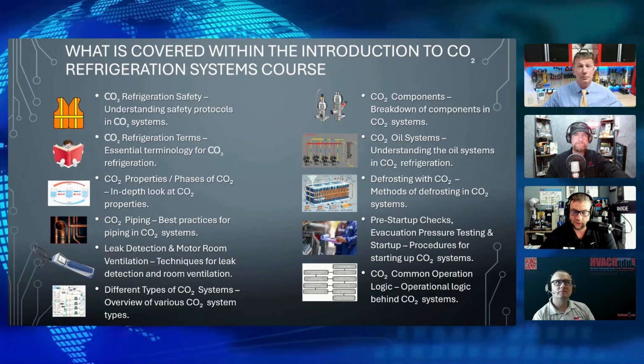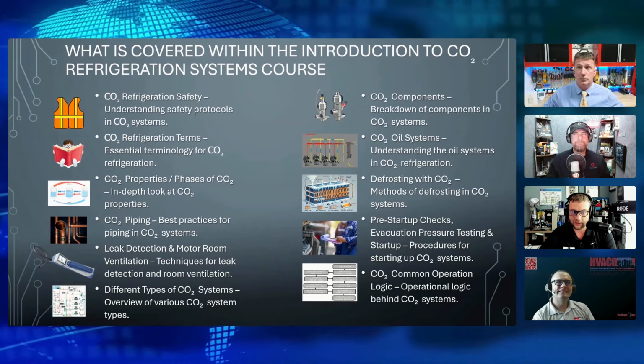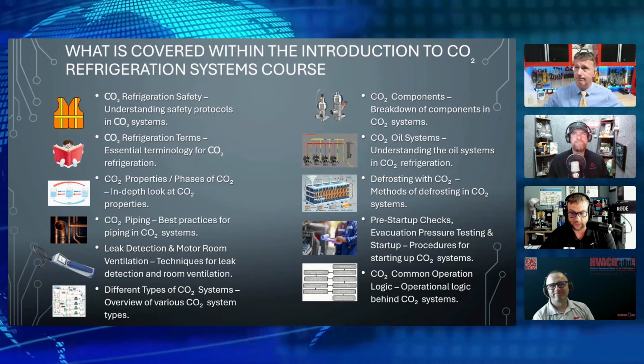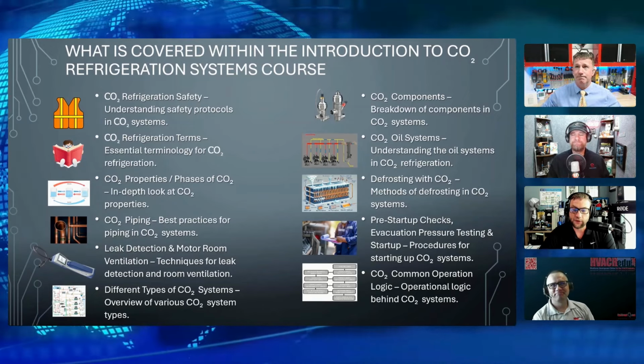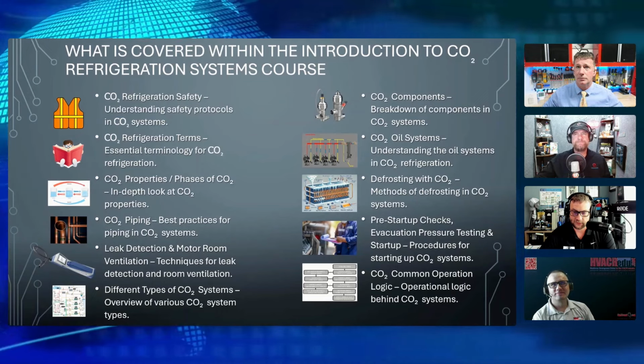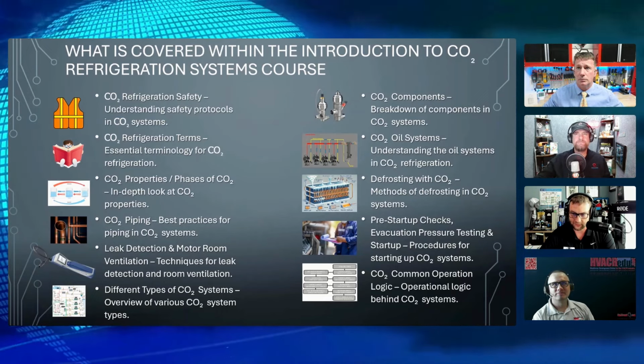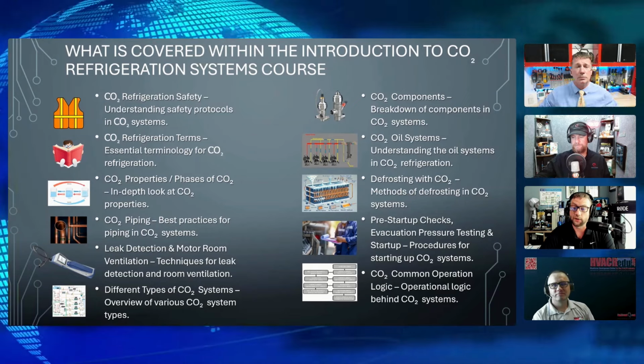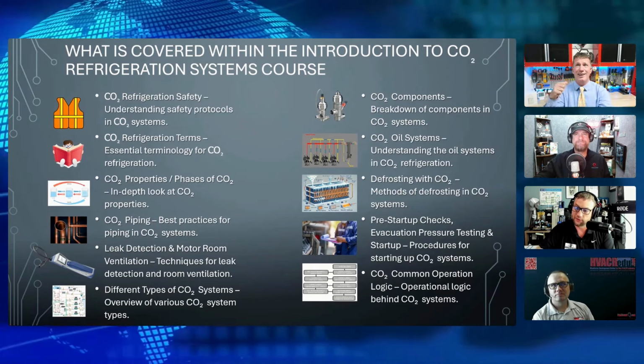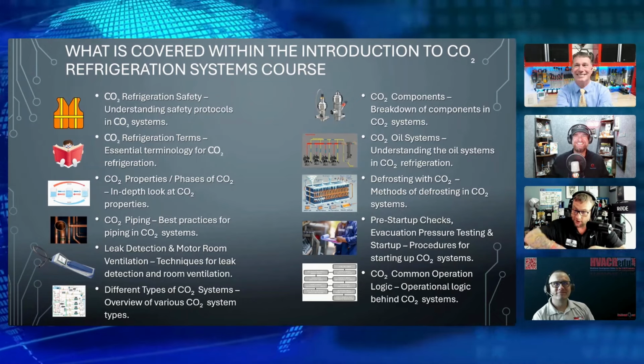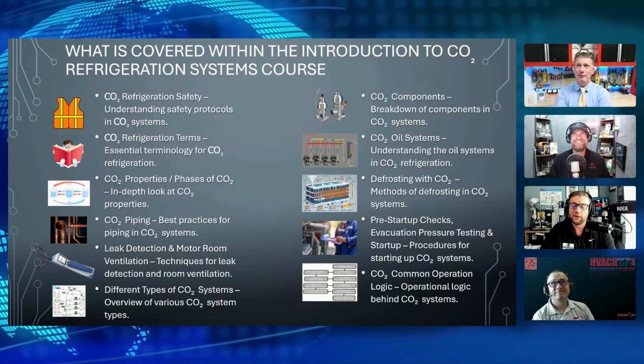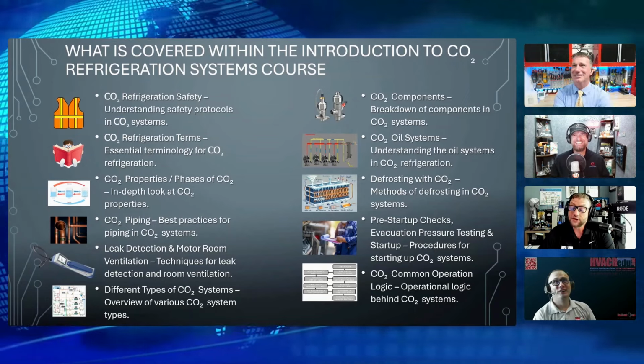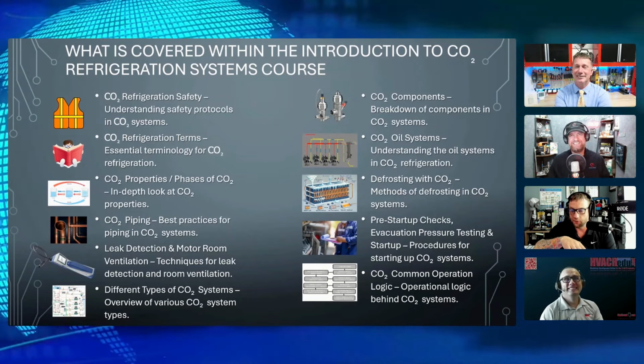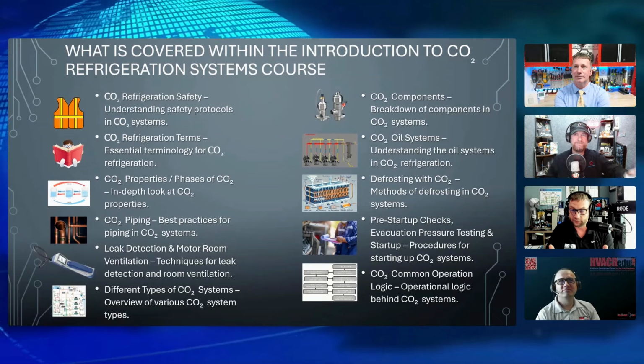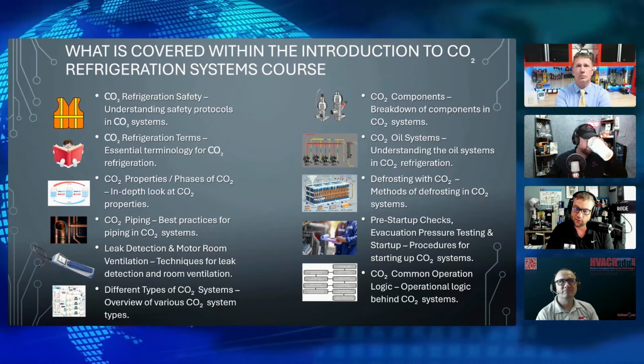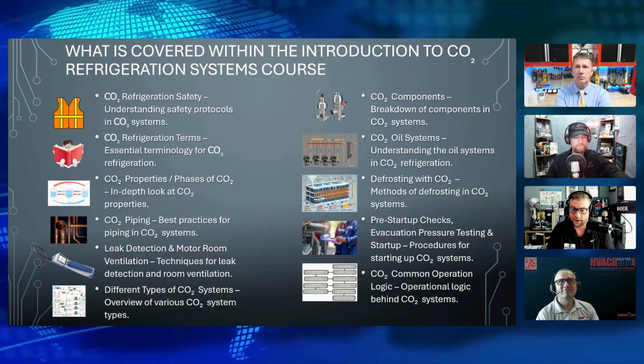CO2 oil systems, as you probably know, Clifton, oil is one of the biggest problems as far as maintaining and service calls on a rack, and it throws a lot of people for a loop. There are at least five or six different types of oil systems that you could potentially have. I cover the basics of those, and I cover how you add oil. I mean, if I tried to add oil, you're not going to pump that into the system. Well, that's what I'm saying. You're going to have Popeye arms by the time. Yeah, exactly. 500 pounds of pressure on this pump. The seals out of it. I basically give you a valve-by-valve scenario of what you should do in order to add oil without having to get those Popeye arms that Ty has. Fantastic.